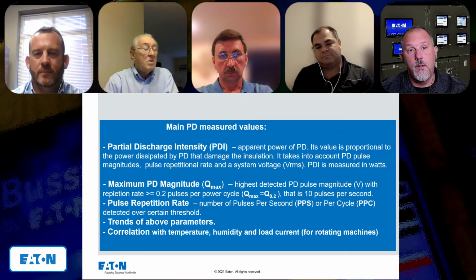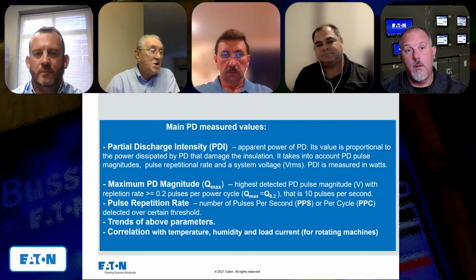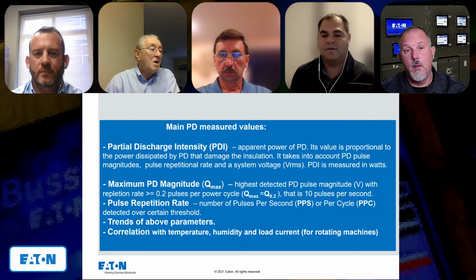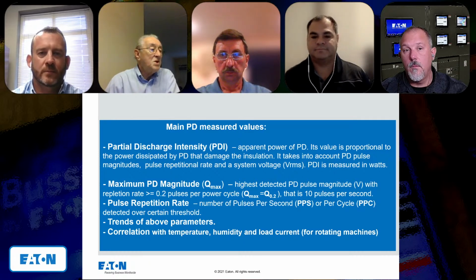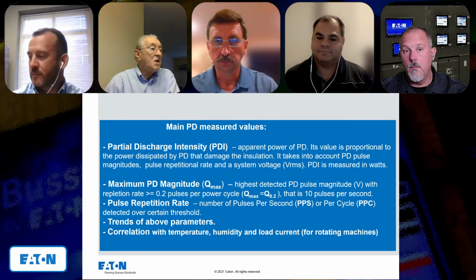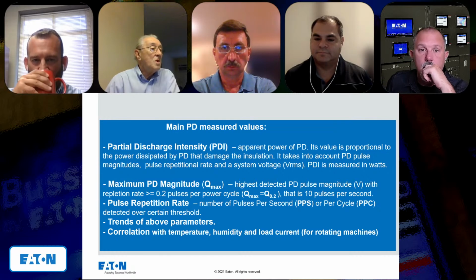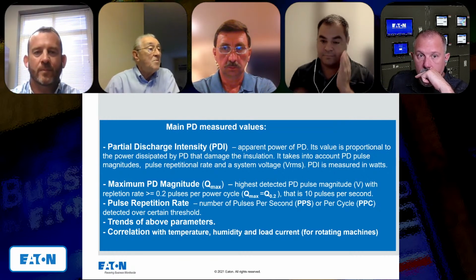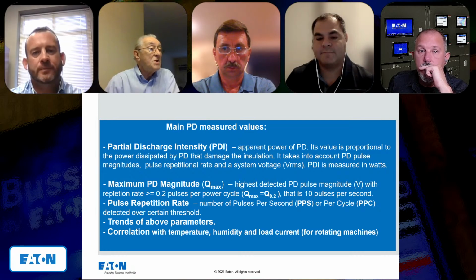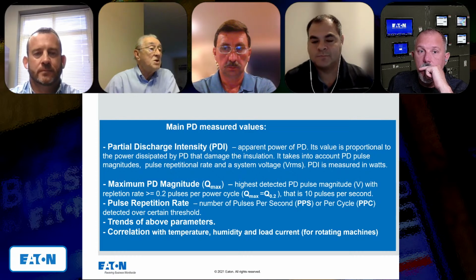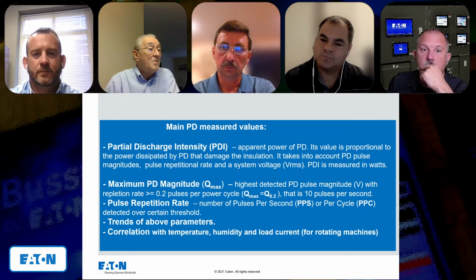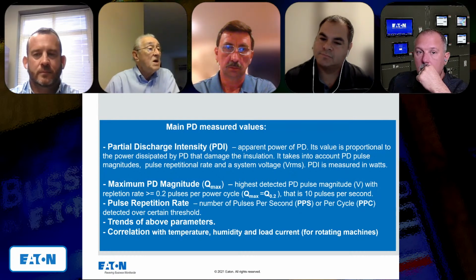No, it is a question. First of all, when we see that the partial discharge strength is very high, we need to check the insulation in the equipment. For example, to see the signs of partial discharges as powder, like we saw before. But the second task is to find the place where this partial discharge originated. And it is a very hard task.